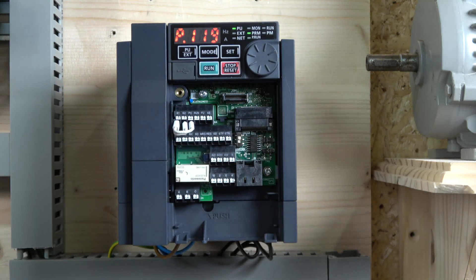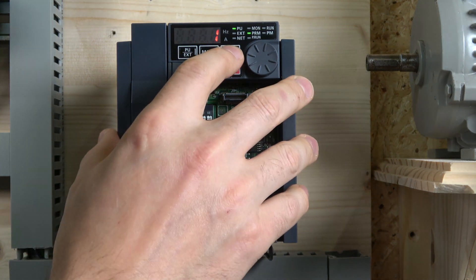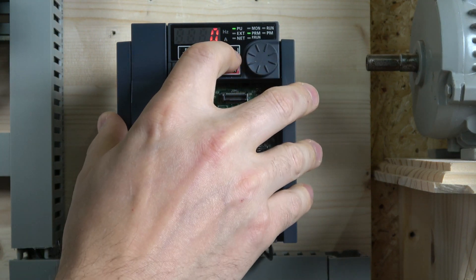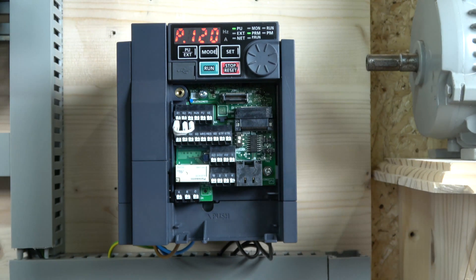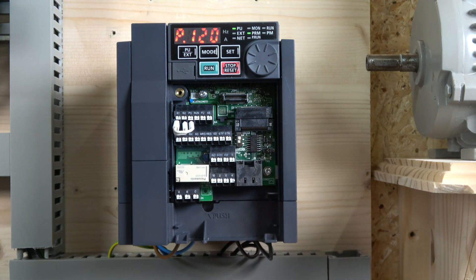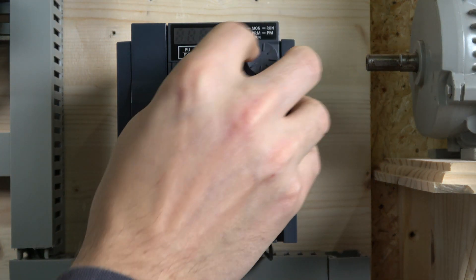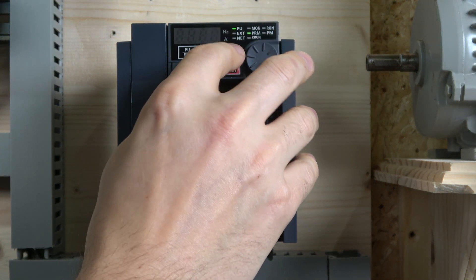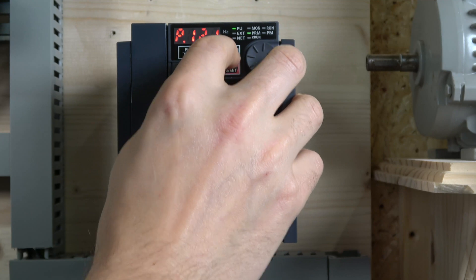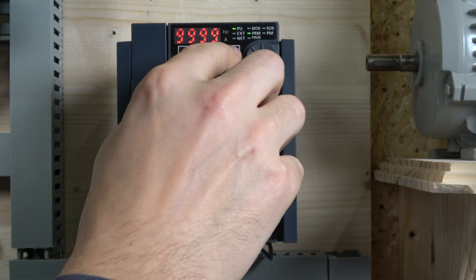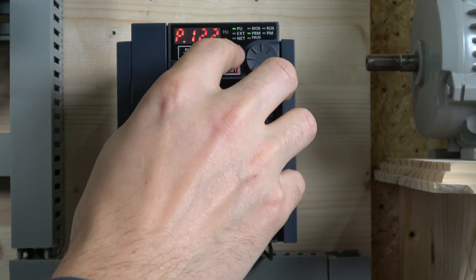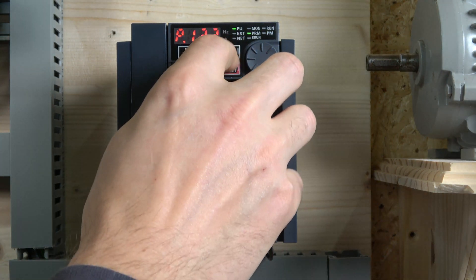The next one is 119, we need to make sure that's at 0 and set that. Next is 120, that should be set to 1. Then 121 set to 9999, and 122 set to 9999 as well. You can do all this quickly in FR configurator, but for the first setup we're doing it from the drive.